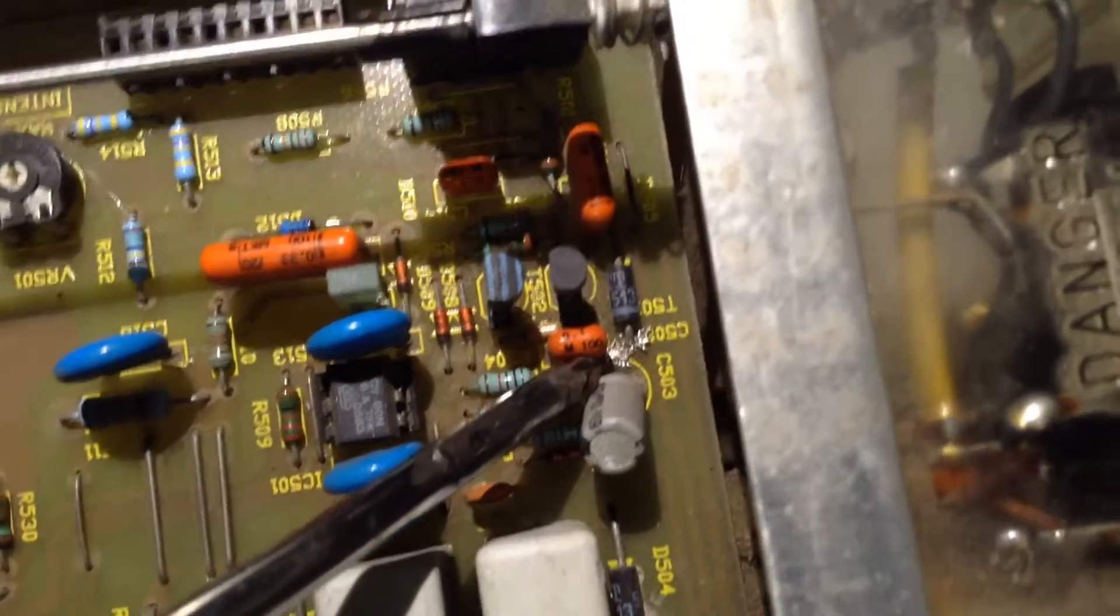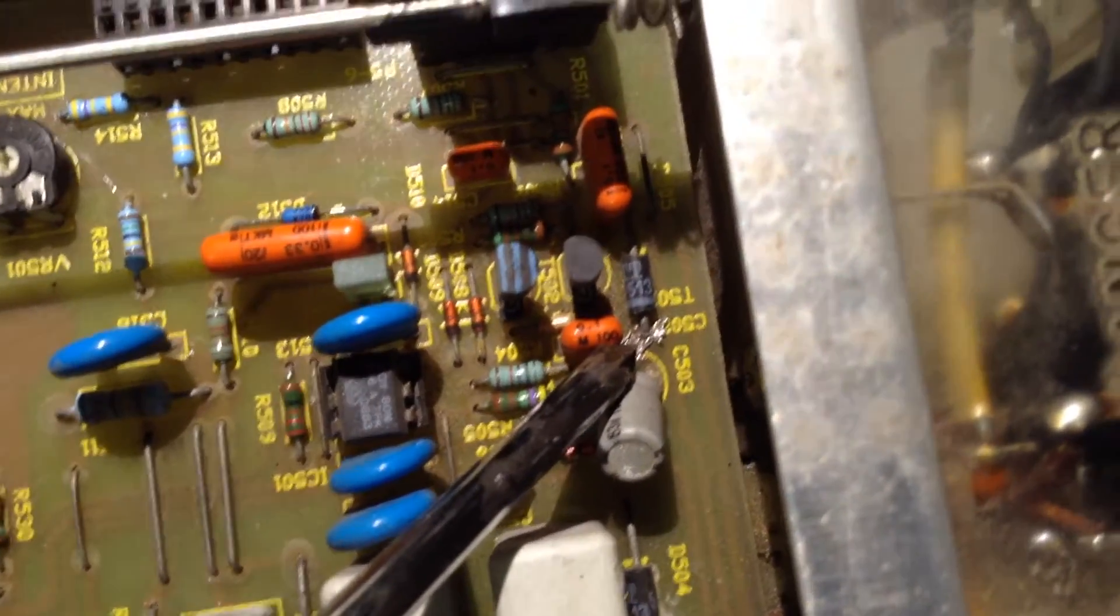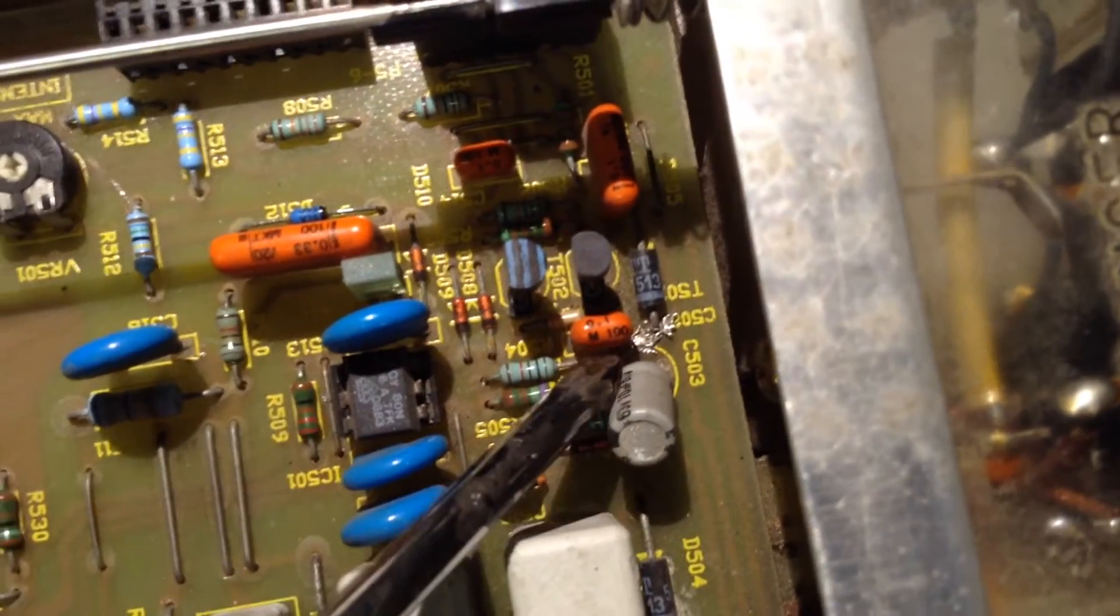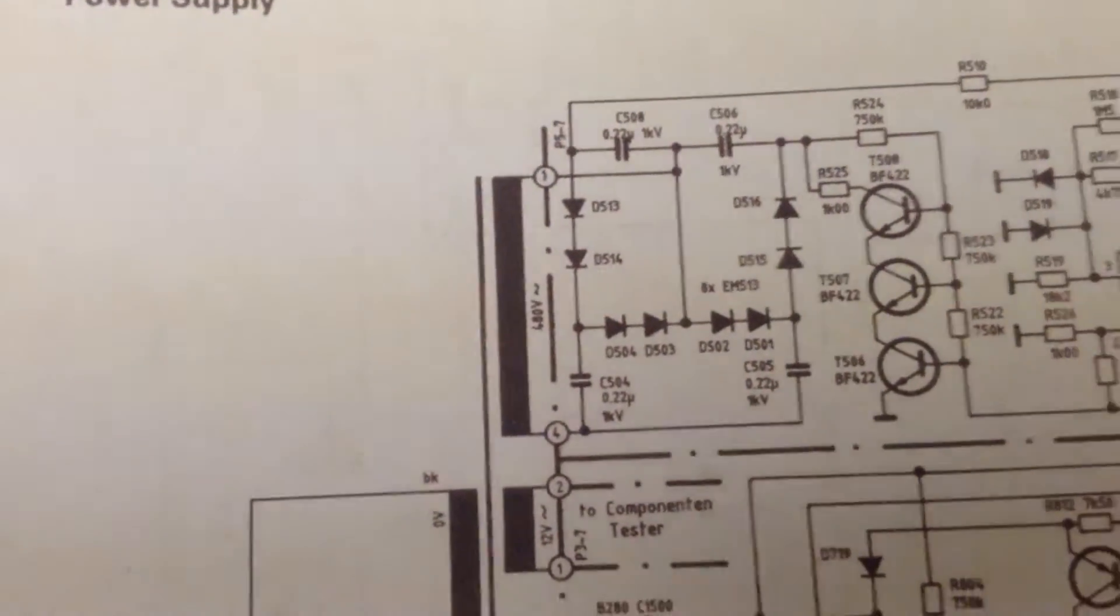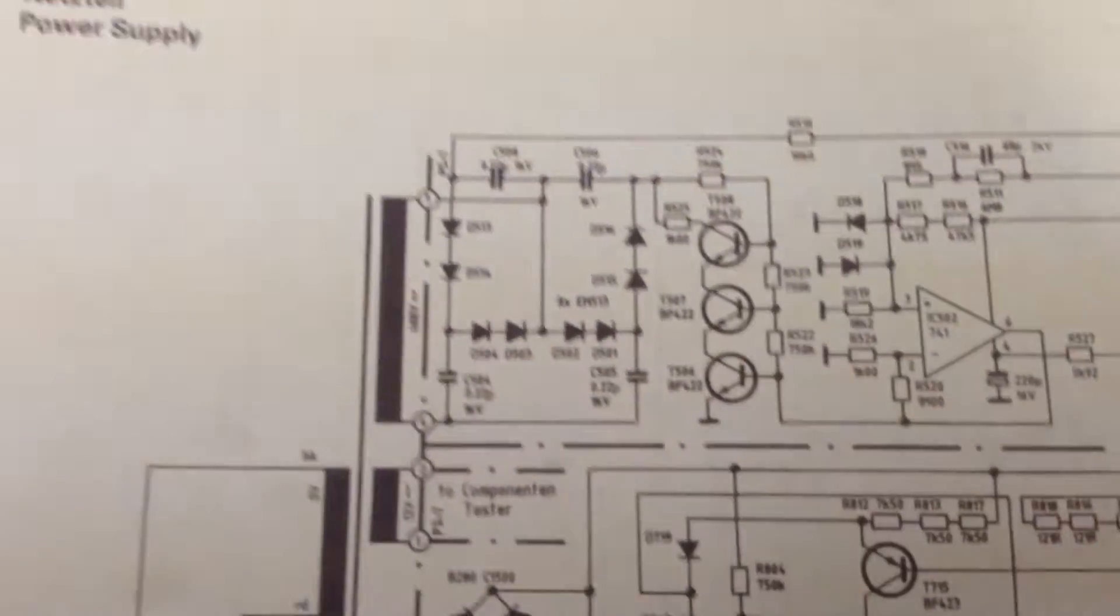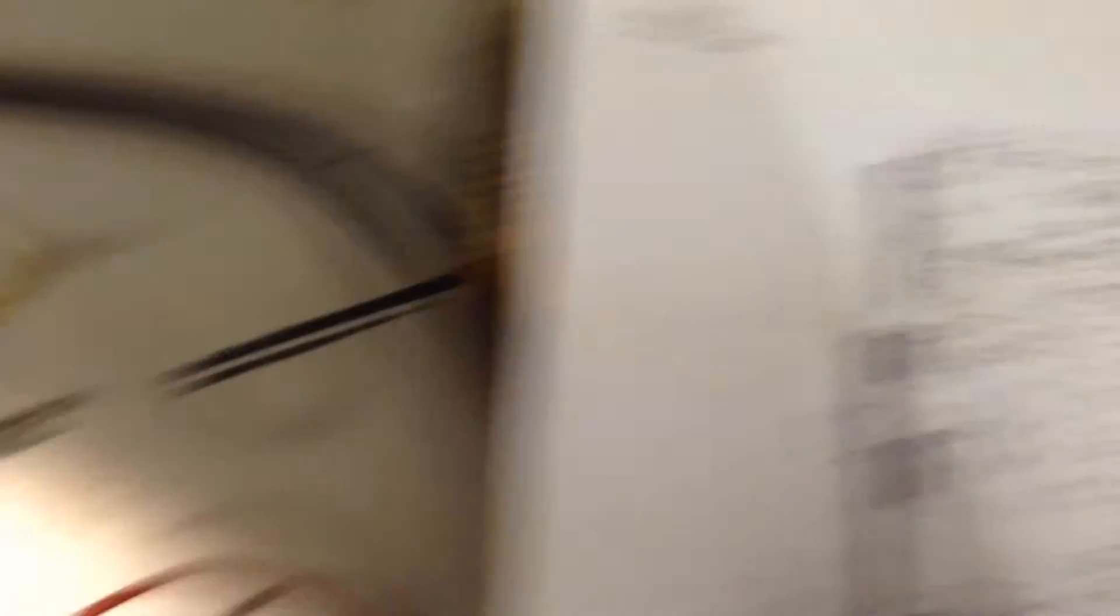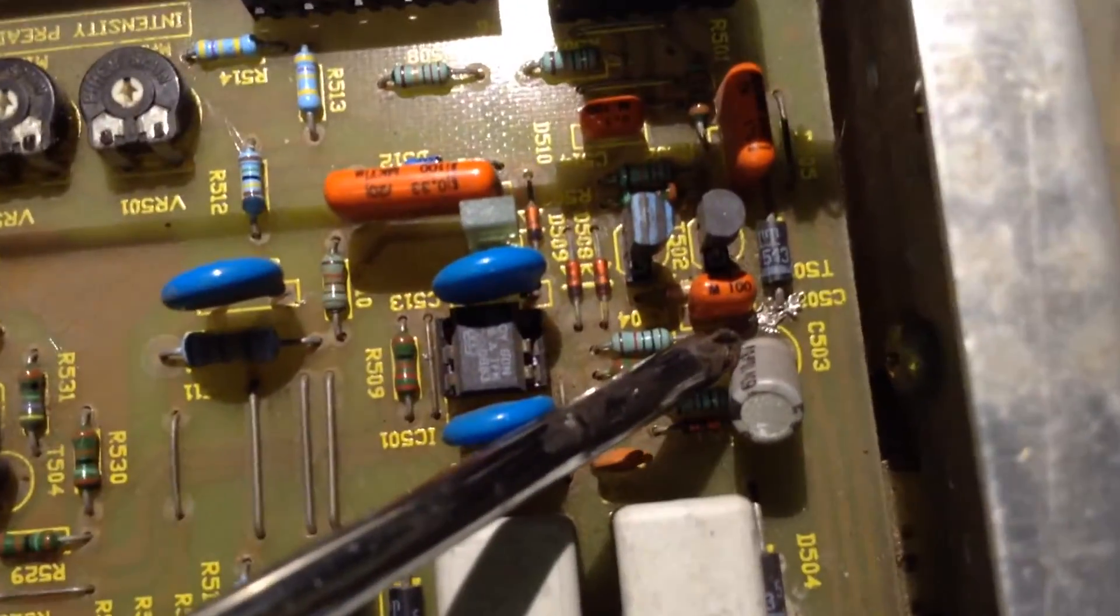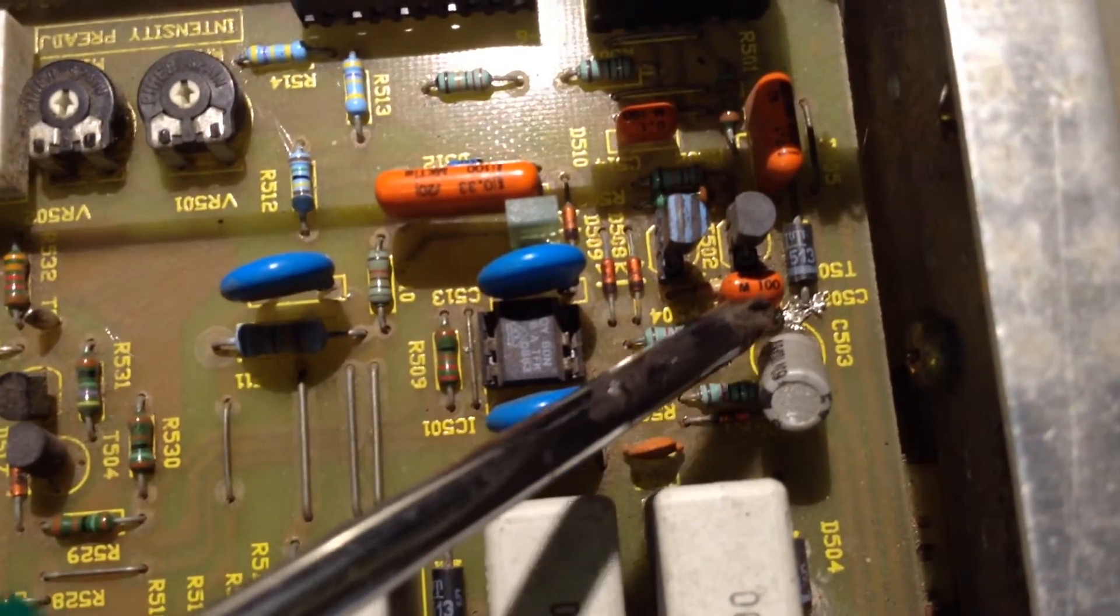Remember that piece of solder splat I picked up? Yeah, it did come from out of here, and look what the freaking heck's happened here. That is a big solder splat. That is a possible cause. I was just about to measure the 400 volts AC, or 480 volts AC coming into this voltage multiplier. It looks like a voltage multiplier. It's just a big bank of diodes and capacitors. And so that looks like a problem. For God's sake. I'm going to find out what's caused that and see if I can clear it up.